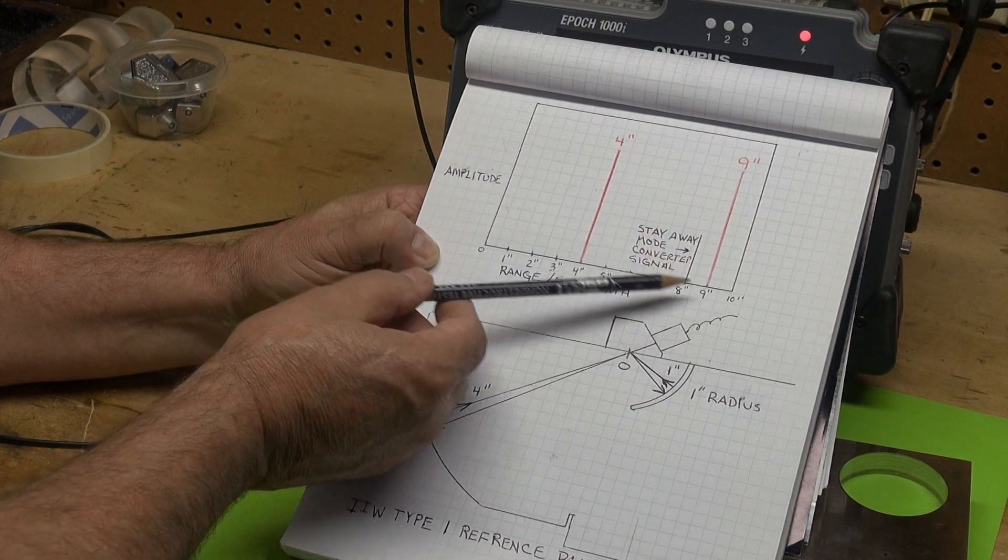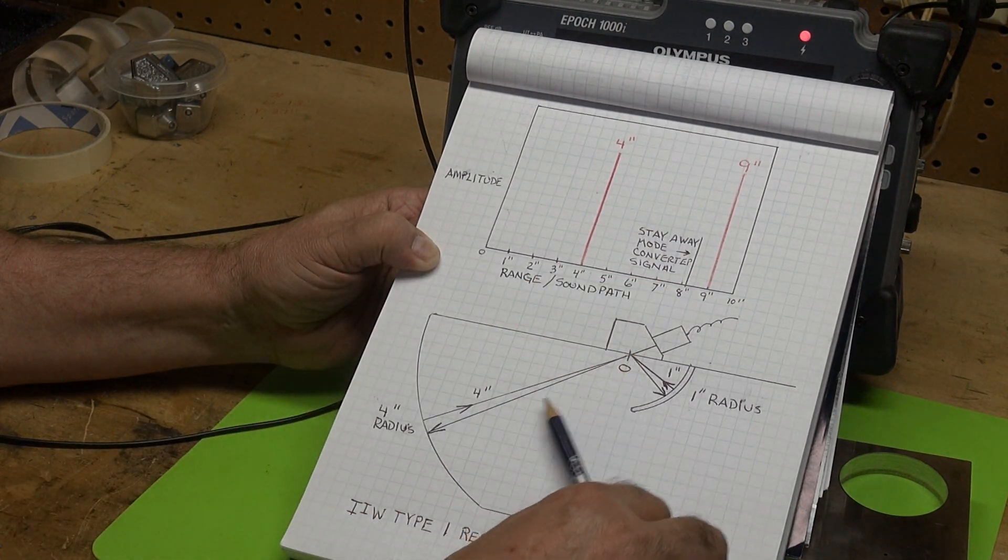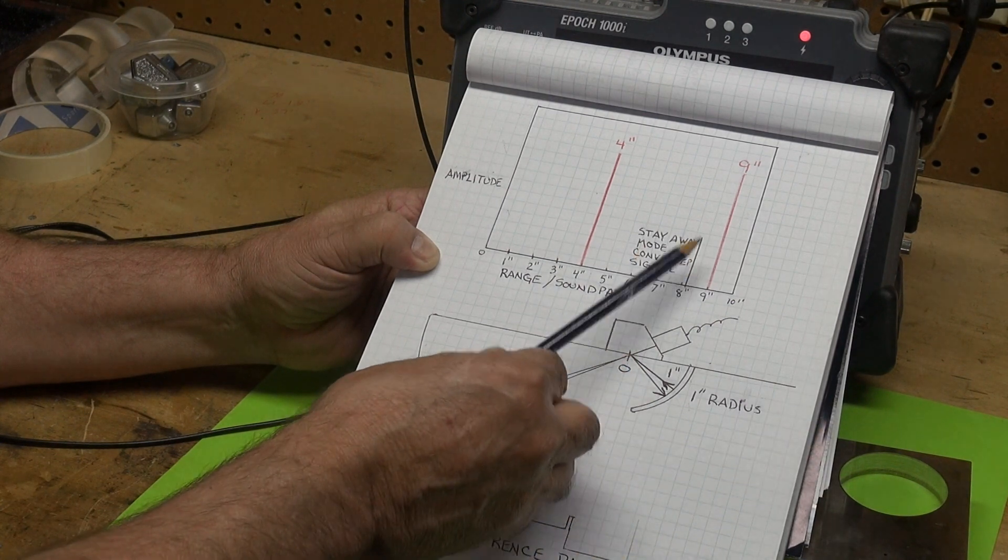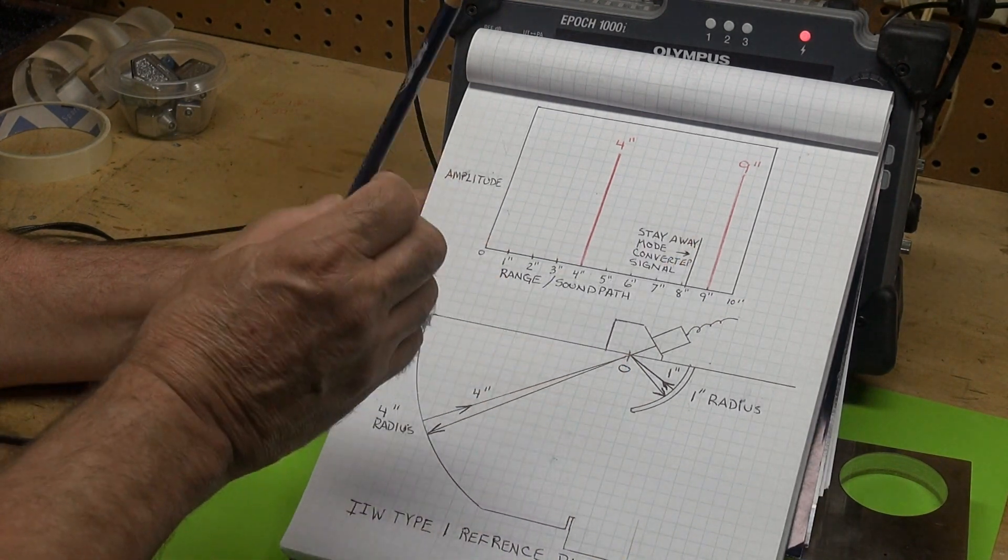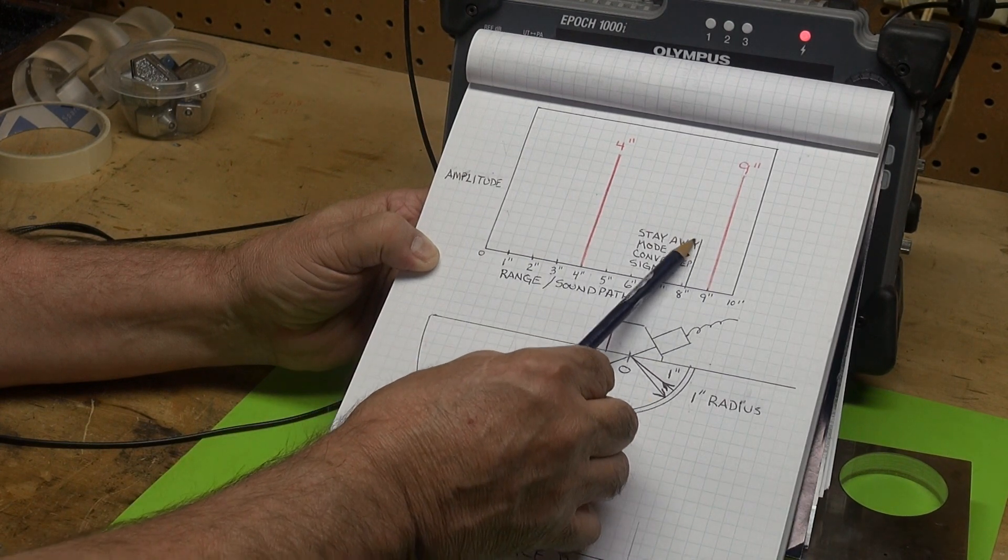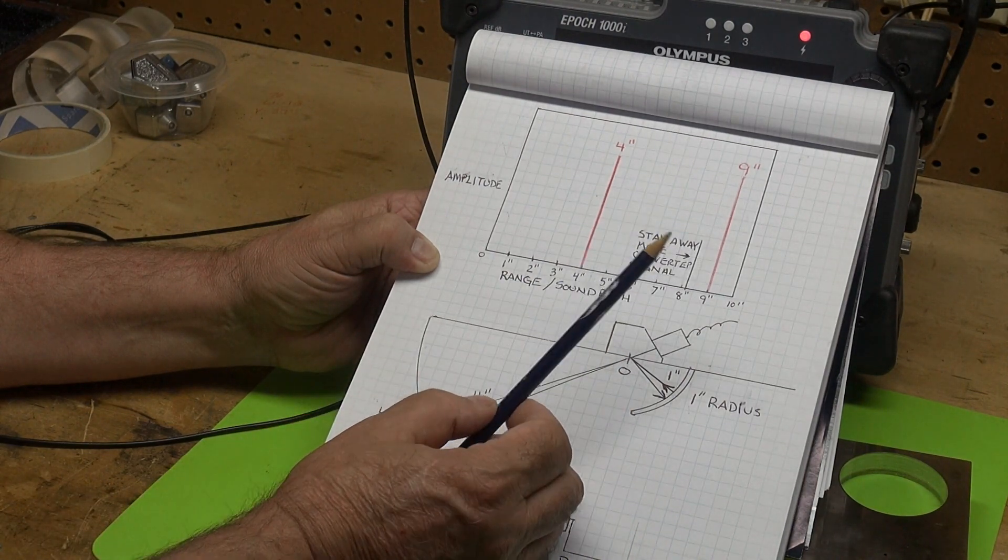Stay away from that as a mode converted signal. Because of the sound path at 9 inches, we're bouncing off the side of this block. It's only an inch wide, so we're getting a mode converted signal. If you're not careful when you calibrate and you grab this, you're going to have a problem.